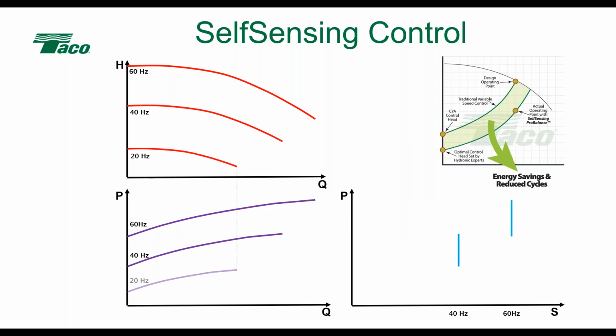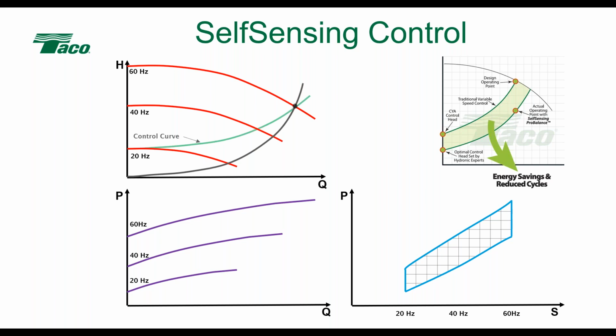And so what we're going to do is we build out through this. What we're going to see is that at these different operating points, there's our control curve and our system curve laid into this for speed curves and power curves. Okay, so you notice speed curves are going from top left to bottom right, and power curves are going from bottom left to top right, because as we move further right on the curve, the power draw is going to go up. Okay, so what happens is we've got all these points plotted. We plotted that pump curve in there. Okay, so we know what all these data points are.